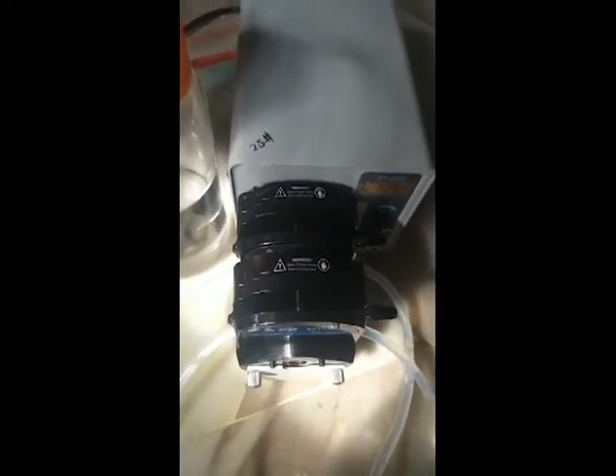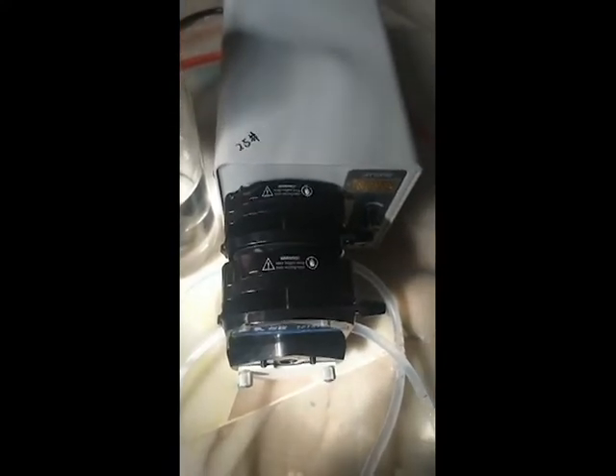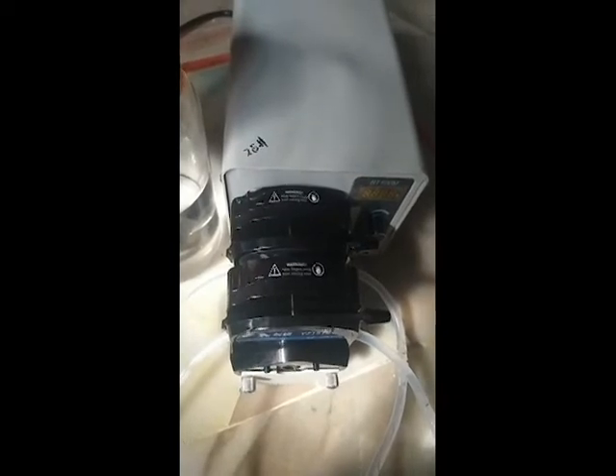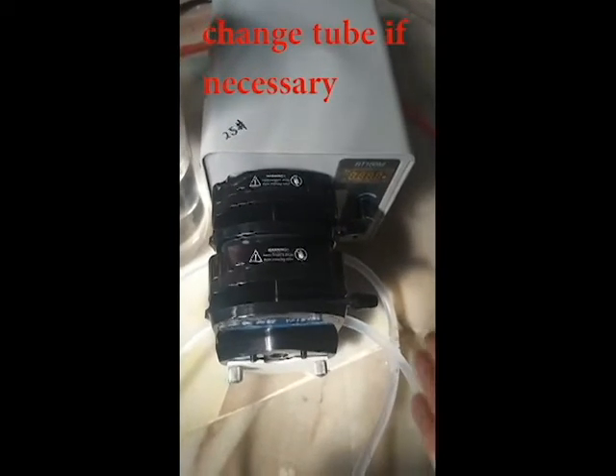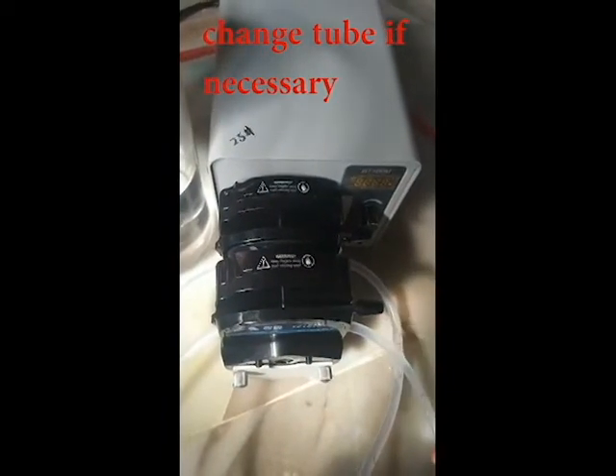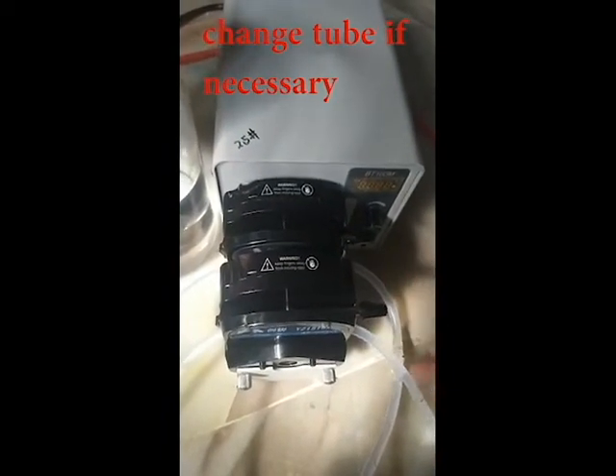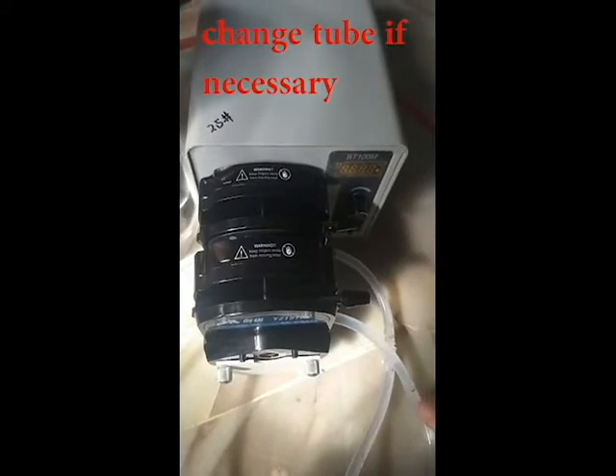This A16G has a much longer life, but you still need to double check the quality of the tube. After some time of use, you need to make sure the tube can really withstand every batch. If it can't, you need to change your tube. When you change your tube, you return all the liquid back to your storage bottle, and you can take the tube out and replace it with a new tube.